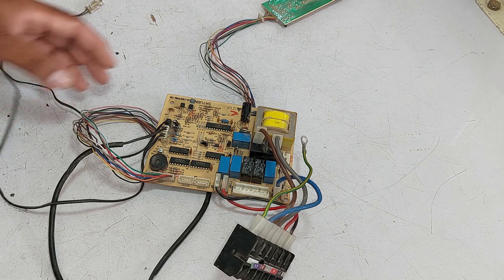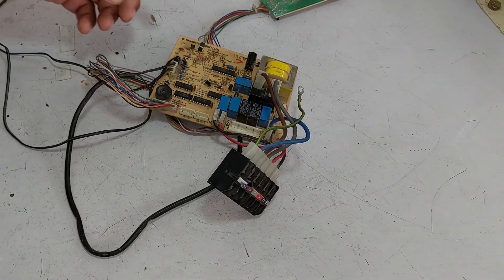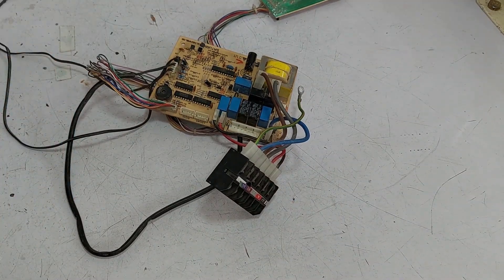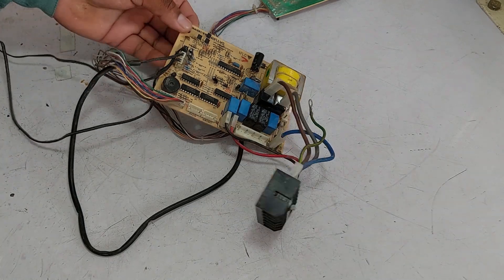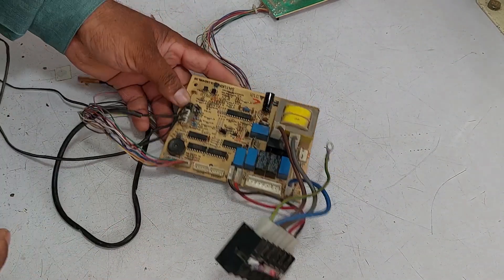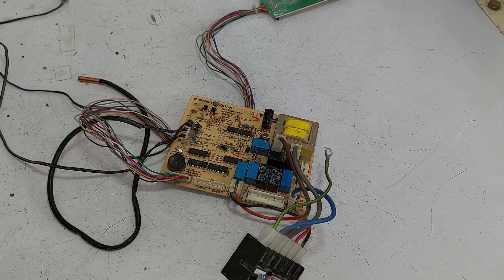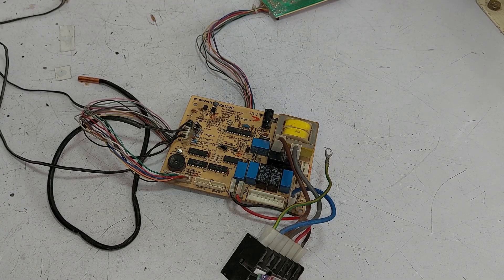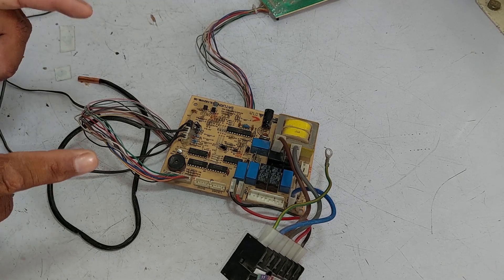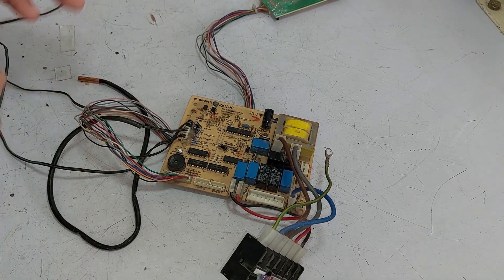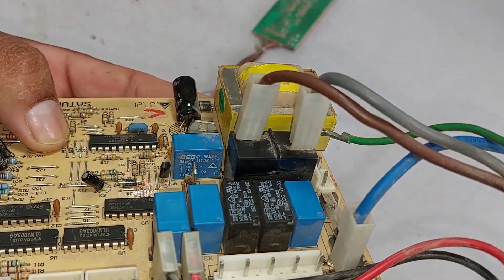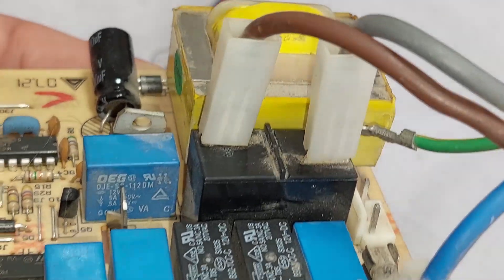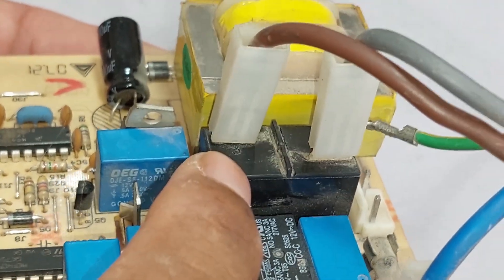Now let's discuss the second reason why ice forms on the suction pipe. First, let's look into the reason behind this issue. In 1.5 ton and 2 ton units, the system is controlled by a PCB, but in 1 ton and some 1.5 ton units, there is often a relay-based system. Here we are dealing with a 20 ampere relay. What happens frequently is that the relay's points get stuck.